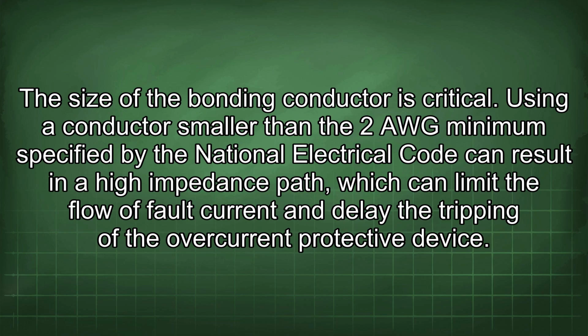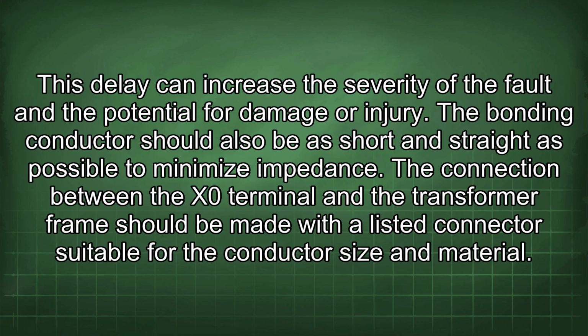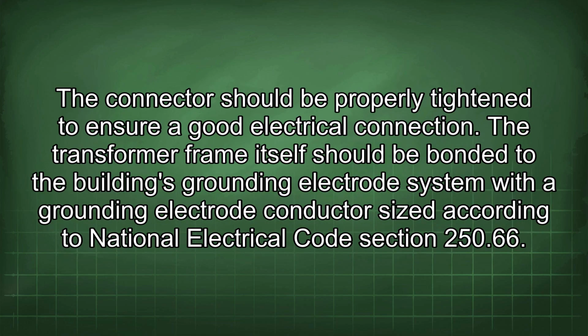The size of the bonding conductor is critical. Using a conductor smaller than the 2 AWG minimum specified by the National Electrical Code can result in a high impedance path, which can limit the flow of fault current and delay the tripping of the overcurrent protective device. This delay can increase the severity of the fault and the potential for damage or injury. The bonding conductor should also be as short and straight as possible to minimize impedance. The connection between the X0 terminal and the transformer frame should be made with a listed connector suitable for the conductor size and material. The connector should be properly tightened to ensure a good electrical connection.